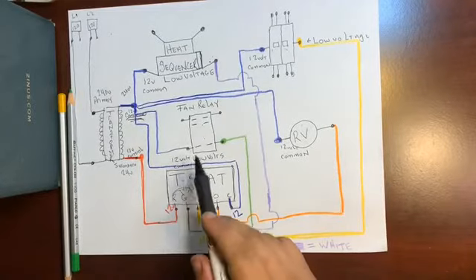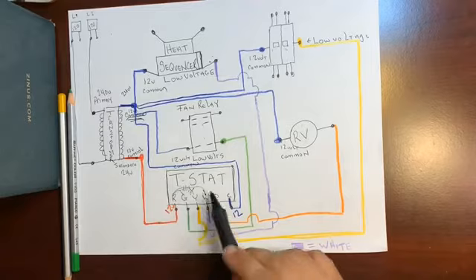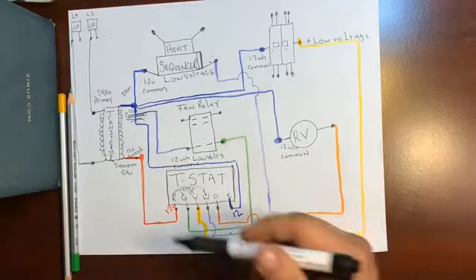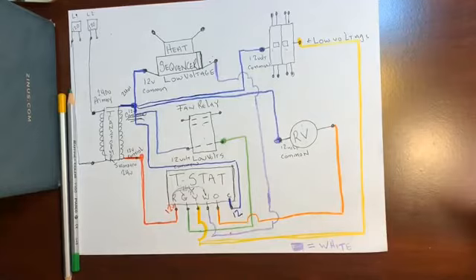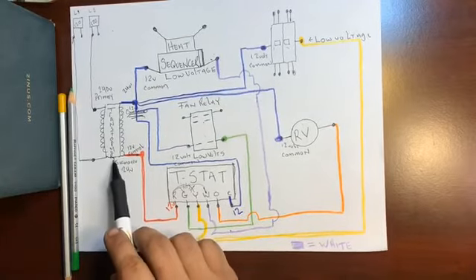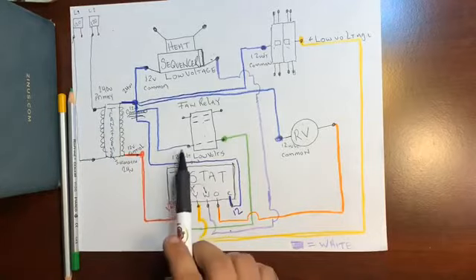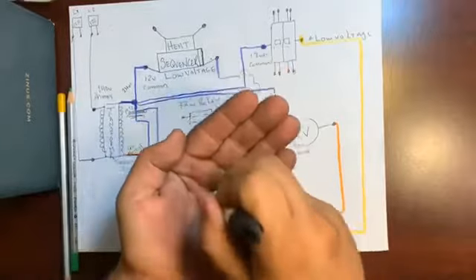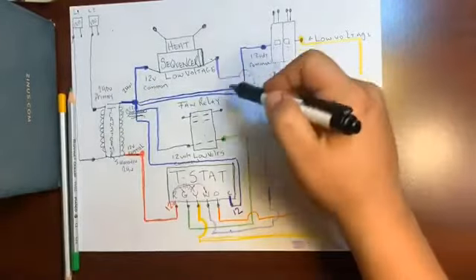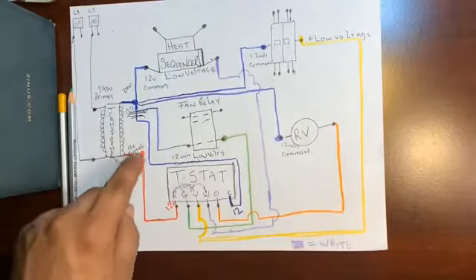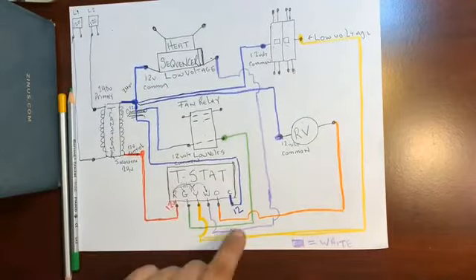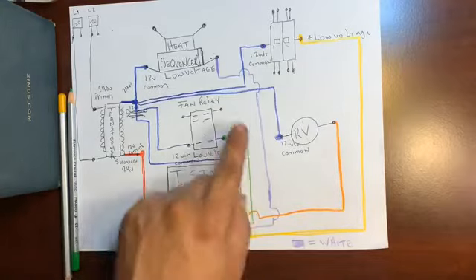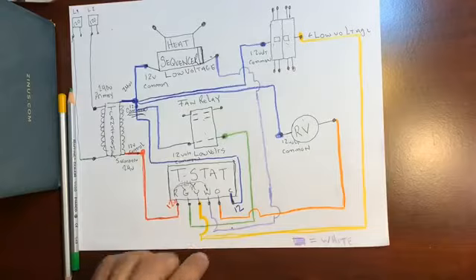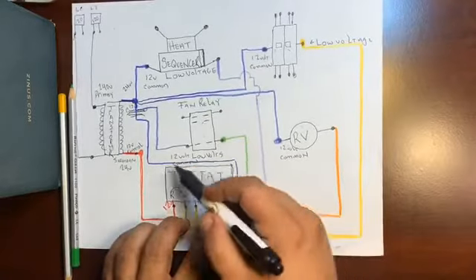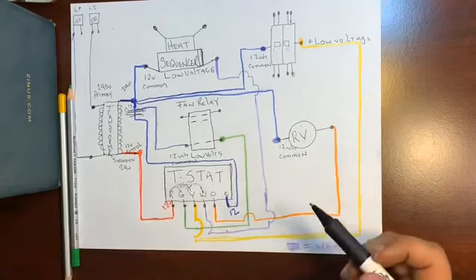If we didn't have low voltage, what that means is there would be 120 volts going through your thermostat to try to control everything in the air conditioner, and homeowners would electrocute themselves. That's why we use a step-down transformer to get ourselves down to 24 volts, make sure every relay has the common in my hand. I cannot stress it enough. Every relay gets its 12 volt common. And then the control goes through the thermostat, and then to the green wire, yellow to the contactor, white to the heat sequencer, orange to the reversing valve, and there's always a gap there in C for 12 more volts, so to make sure the thermostat has 24 volts.